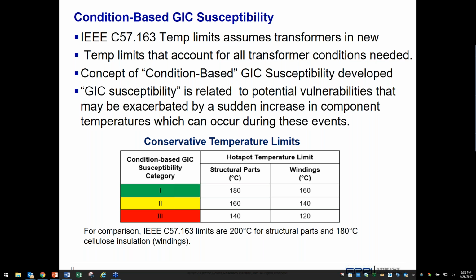We lowered it again for level 2, which I would call medium range condition transformers. And then for level 3, we lowered it again. The level 3 transformers were those that are much older or generally in poorer condition. So we have basically good, fair, and poor conditions, and from that, we changed the temperature setting. Essentially, we said if a poor condition transformer were forecast to reach 140 degrees Celsius, we would begin to see damage to the structural components of that transformer. So that's the basis for our assumption.